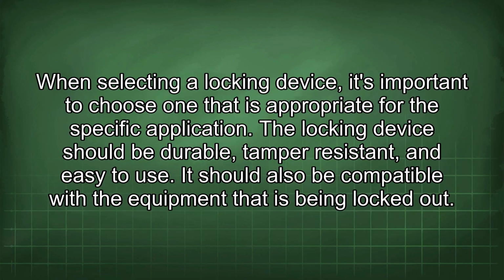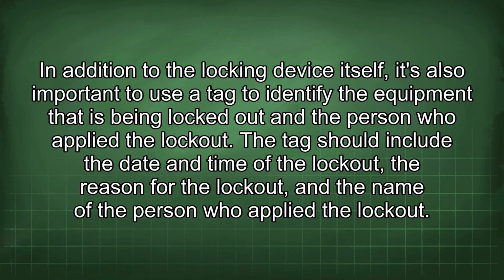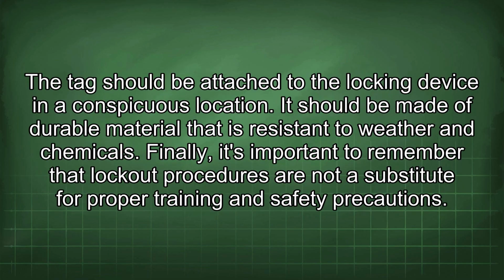When selecting a locking device, it's important to choose one that is appropriate for the specific application. The locking device should be durable, tamper-resistant, and easy to use. It should also be compatible with the equipment that is being locked out. In addition to the locking device itself, it's also important to use a tag to identify the equipment that is being locked out and the person who applied the lockout. The tag should include the date and time of the lockout, the reason for the lockout, and the name of the person who applied the lockout. The tag should be attached to the locking device in a conspicuous location. It should be made of durable material that is resistant to weather and chemicals.